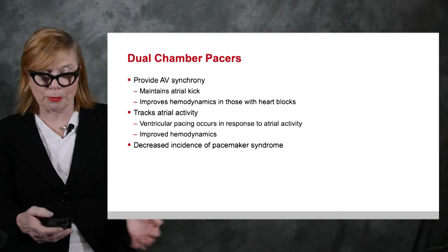Okay, so remember, the AV interval is the period of time between the atrial event, either sensed P wave or atrial pace, and a paced ventricular event. The VV interval is the period of time from ventricular complex to ventricular complex. So if I fire my own ventricular beat, the VV interval is when the pacemaker will next fire from intrinsic beat to paced beat. So it's really a compensatory pause. And the VA interval is the ventricular complex till the next atrial activity. And that's called the atrial escape interval. If my patient fires his own P wave before that interval is exceeded, you will inhibit the pacemaker firing.